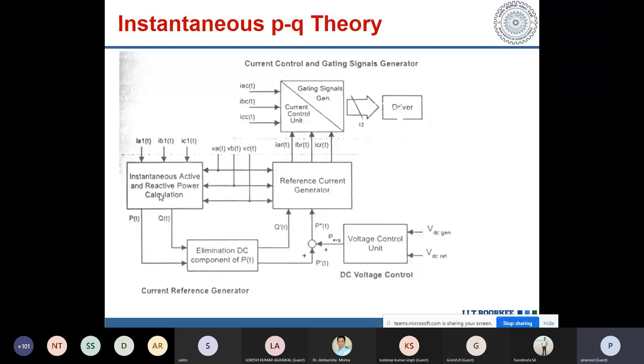So from this instantaneous power that we are getting, if we can find the average value, that average value is the average power going from the source to the load. Using a filter, we can find the DC component of the instantaneous power. From that component, if we divide by the sinusoidal voltages VA, VB, VC, we will get the sinusoidal currents IA, IB, IC. Then we can take the difference of these currents with the actual load current, and we will get the harmonic currents.